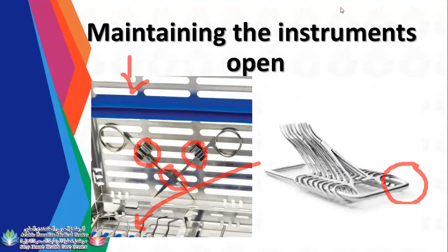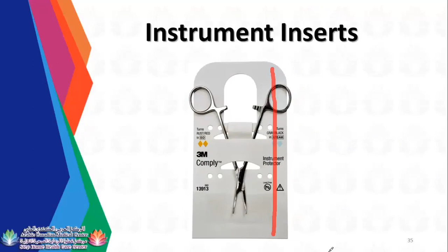So there are some inserts, which can still maintain the instruments open. If you are using inserts, guys, you are not allowed to fold these inserts and place them in a pouch. They should remain as they are. For example, you will place this instrument directly in a pouch which will fit these inserts. But you cannot fold here or here just to fit these inserts into a certain pouch. You are not allowed to do it.